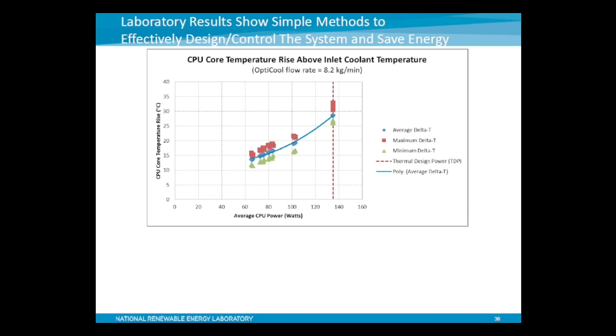This graph represents the culmination of the experimental data, showing the average CPU or central processing unit power as reported by the server system in a software utility we partnered with Intel to use, plotted against the CPU core temperature. This shows that with the LiquidCool Solutions technology, we can maintain, under typical applications, a CPU temperature that's 20 degrees C warmer than the fluid temperature. That's actually a very good heat transfer characteristic, since an air-cooled system requires the electronics to run 50 to 80 degrees C above the incoming air temperature. That's where the real advantage of liquid cooling comes in.